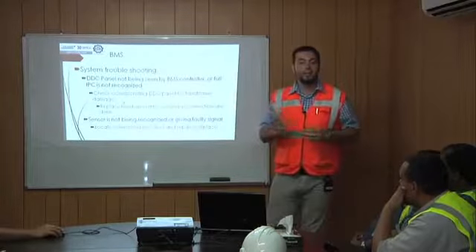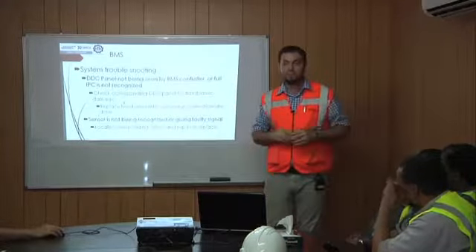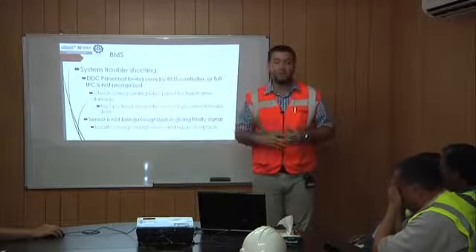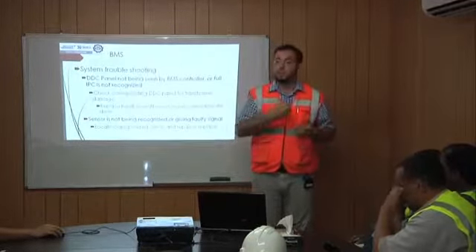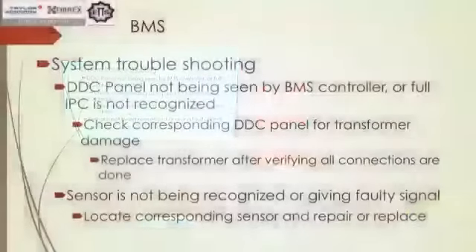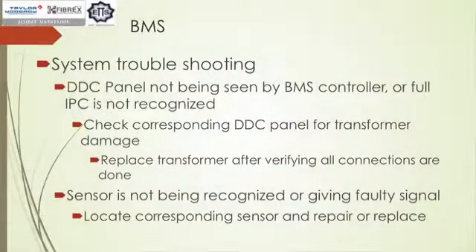Let's say we get an error on a specific sensor. We're trying to access the RTU, let's say the fresh air damper. We're clicking on it, nothing is happening. We need to go back to the RTU and check this sensor or this damper or this actuator to actually know what the problem is and replace it accordingly.